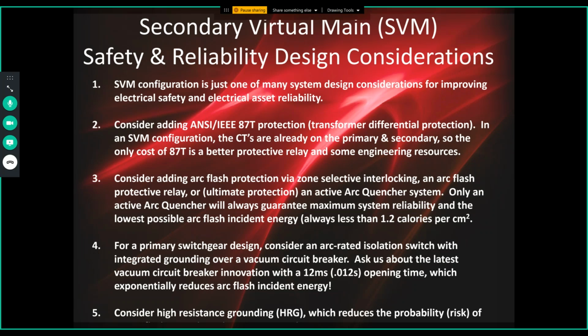87T for a transformer. I would consider adding arc flash mitigation protection either via zone selective interlocking, an arc flash protective relay, or, if you're in a critical process environment, an active arc quencher system, which of course always guarantees, in all application environments, an available incident energy below 1.2 calories per centimeter squared. So active arc quenchers are the only solution prior to doing a power system study that we can tell you in 100% of cases always reduces incident energy below the level where arc-rated PPE is required. And of course, we do separate presentations on active arc quencher systems.